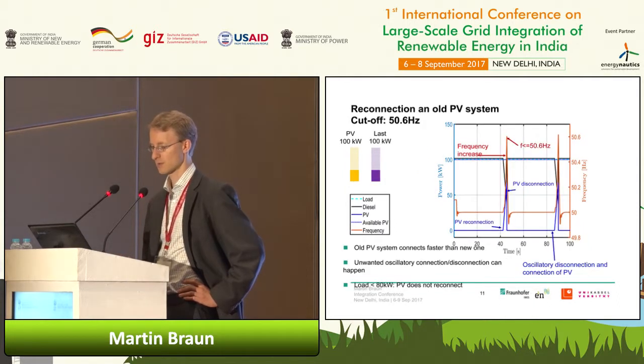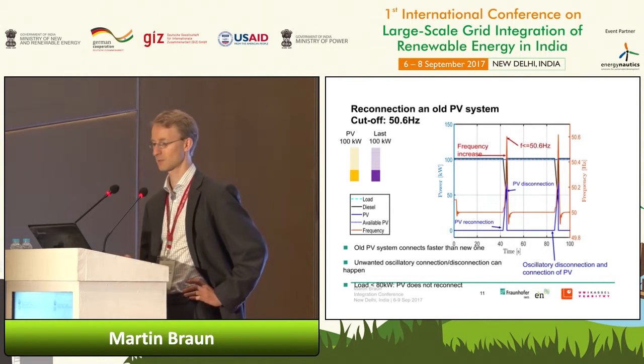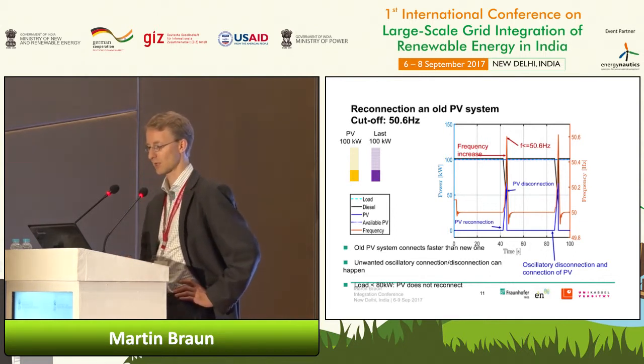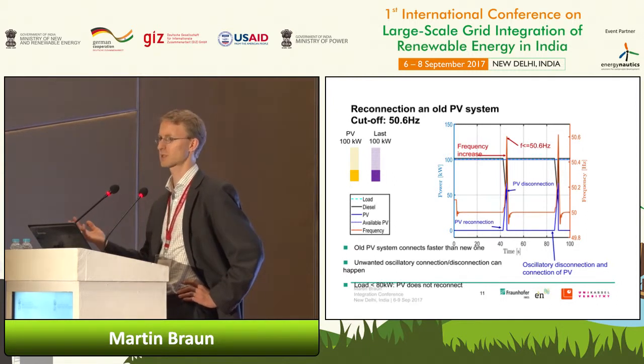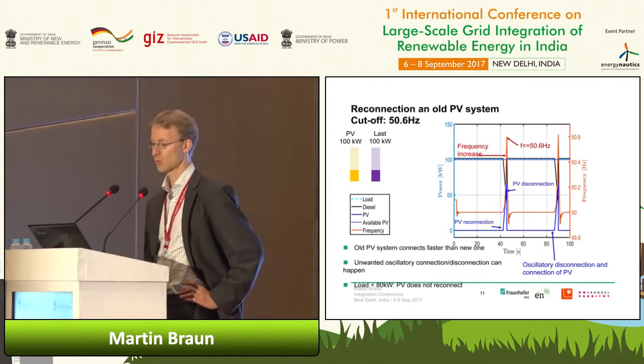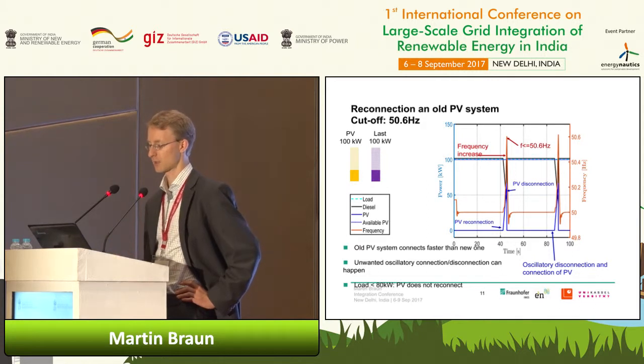However, if we increase the share of PV compared to the load, so it's now equivalent, we can see that it's coming into fluctuation. So the PV system reconnects, then we have a steep decrease of the power of the diesel genset. Thereby the frequency increases, and at 50.6 Hertz we have a disconnection again, and so it is oscillating. So you see, with the old grid code we had in Germany, we wouldn't be able, under high penetration situations, to restart the system towards a stable condition, which means that the result of the new grid code is much better.